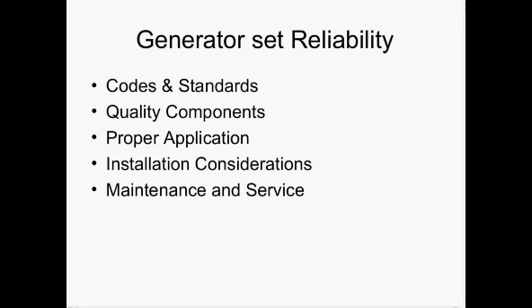The generator set selected for the application must be sized properly to ensure it will perform as required for the loads to be powered.